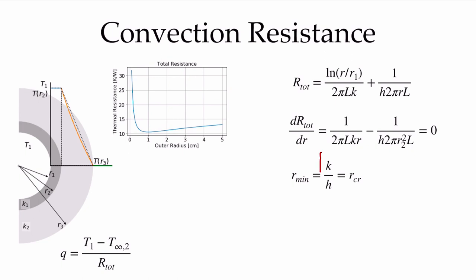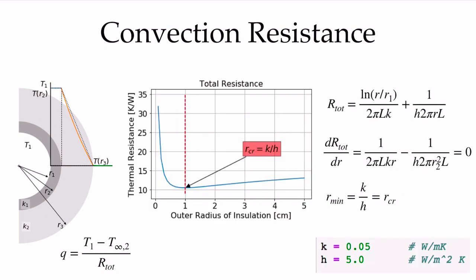If my outer radius is smaller than the critical radius, I'm decreasing the resistance and increasing heat transfer from the system. I must ensure that my outer radius is larger than this critical radius, or it makes no sense to add insulation to the pipe. In our example, conductivity was 0.05 W/m·K and the convection coefficient was 5 W/m²·K, so k/h equals 1 centimeter — exactly where we see this minimum, when the outer radius is 1 centimeter, or the insulation thickness was 0.9 centimeters.